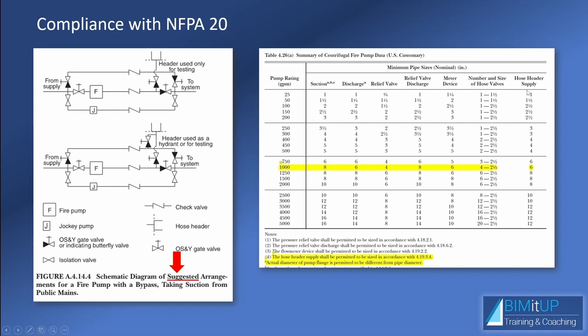And then the number of hoses, like I mentioned, is typically 250 GPM per hose valve. And that's not an absolute truth, but at least it's a good rule of thumb. You can see 250, 1; 500, 2; 750, 3; 1,000, 4; you know, then 1,500, 6. But again, it's not perfect, but it's a good rule of thumb so that you know how much. If you're on the outside of a fire pump room, you may have a good idea of how many GPM are flowing through that pump. And then the hose header supply pipe is going to be 6 inches.